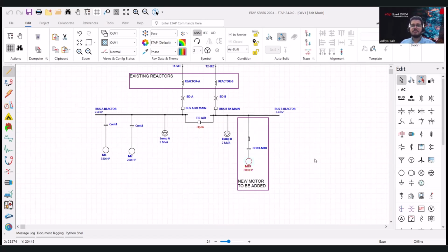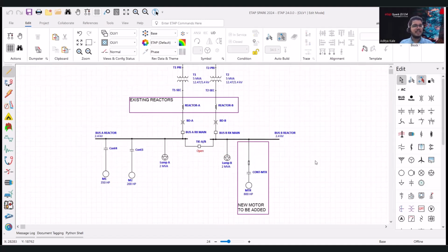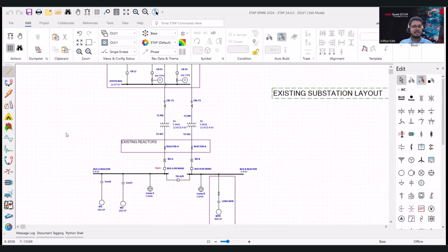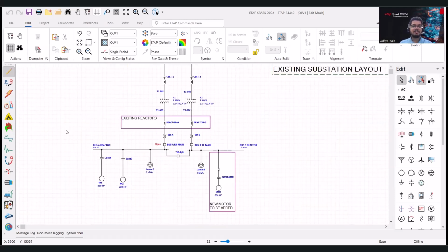This 800 horsepower motor is the new load that is to be added on bus B. Before running any system studies, we have set up all possible configurations for the particular sub. We have a normal configuration where the substation is double-ended, a paralleled configuration during the switching, and a single-ended substation configuration where the entirety of bus A and bus B is fed through one transformer. So let's look at the issue of why we can't start the motor with the reactors in circuit.